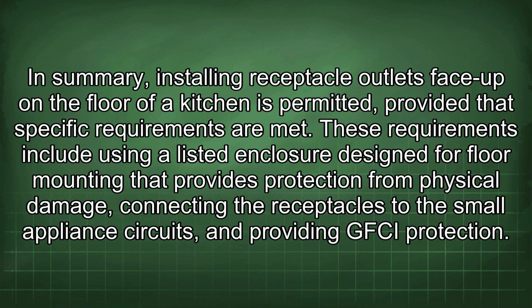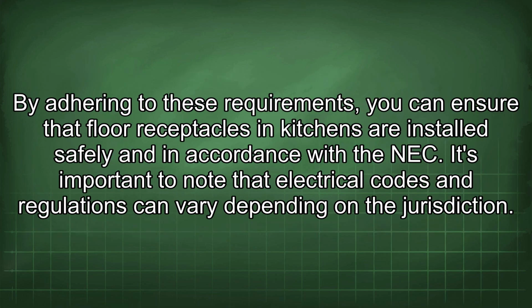In summary, installing receptacle outlets face up on the floor of a kitchen is permitted, provided that specific requirements are met. These requirements include using a listed enclosure designed for floor mounting that provides protection from physical damage, connecting the receptacles to the small appliance circuits, and providing GFCI protection. By adhering to these requirements, you can ensure that floor receptacles in kitchens are installed safely and in accordance with the NEC. It's important to note that electrical codes and regulations can vary depending on the jurisdiction.